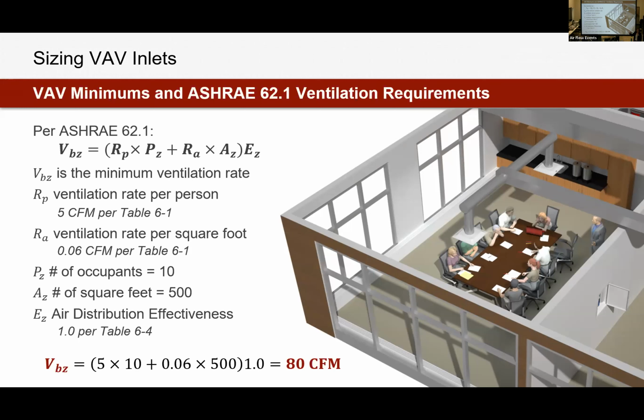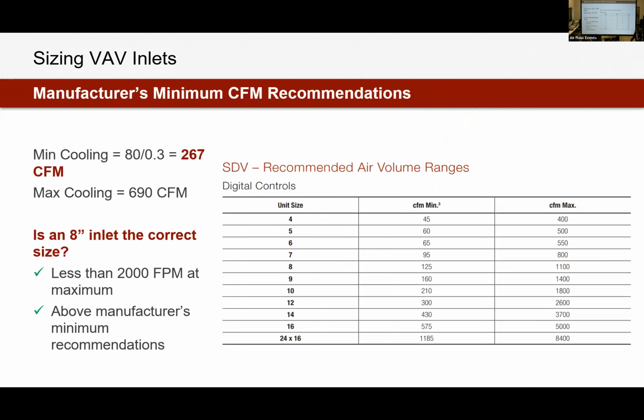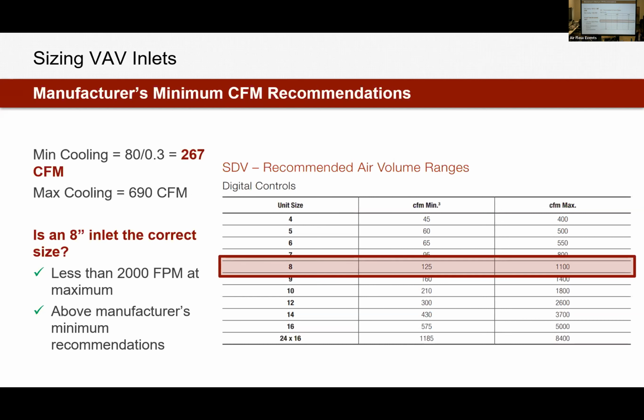So with our 5 CFM per person, we also have an airflow for a square footage. So we've got the people ventilation load and the square footage. From there, we can determine what that minimum airflow is. 80 CFM comes out of that equation. So again, we need to reference back to the catalog to make sure that our size 8 inlet valve can actually achieve this range that we're trying to meet. So we've got our range here, 267 CFM to our max cooling 690. We double check the airflow range on that catalog. We can see that we're going to fit within the range.